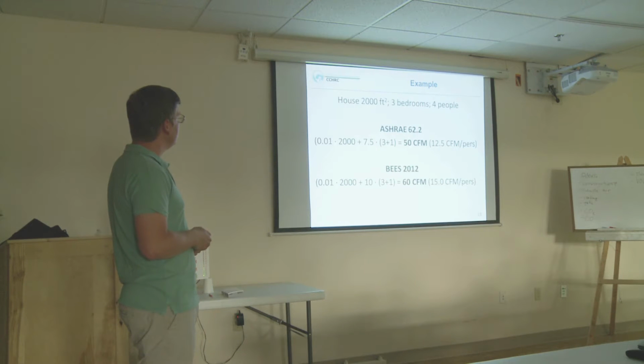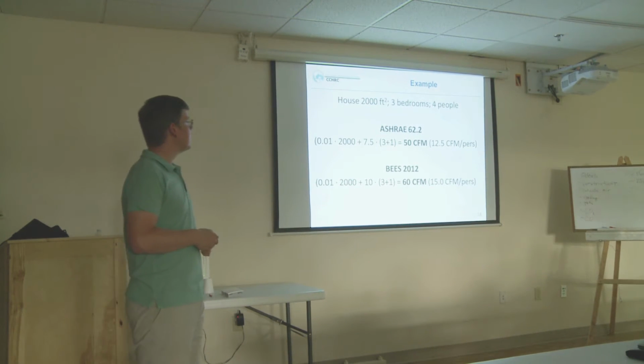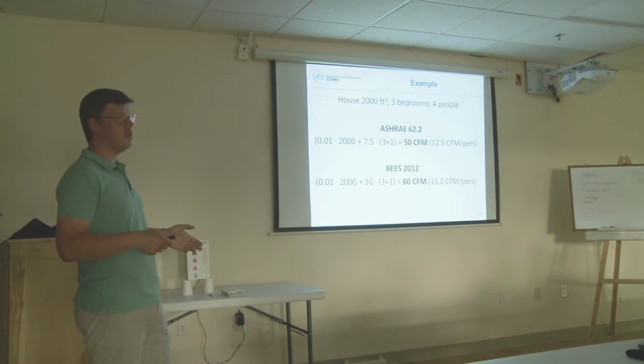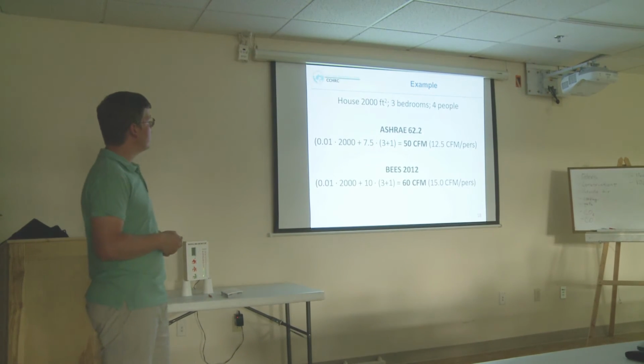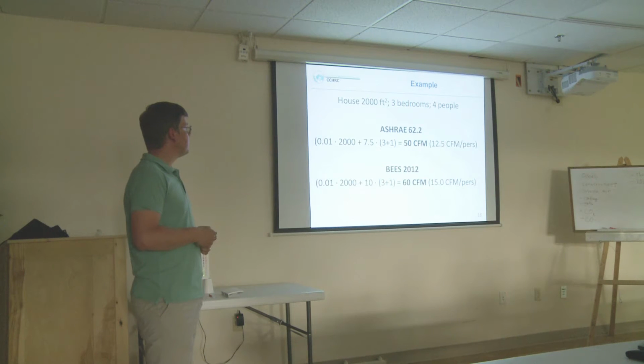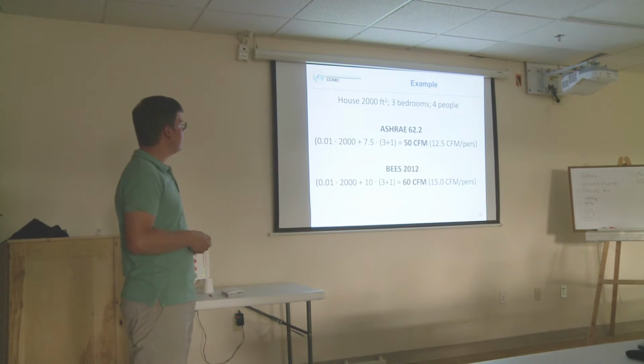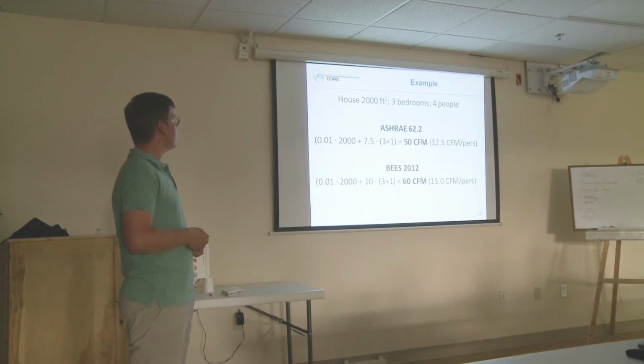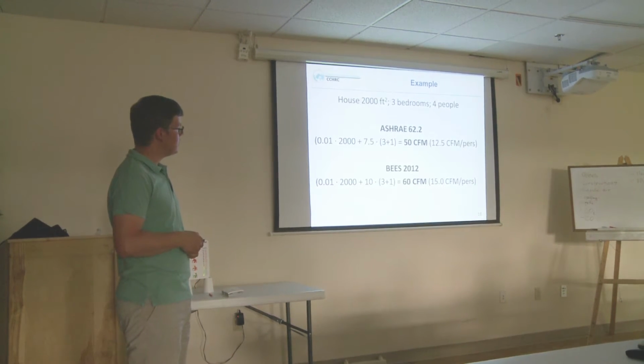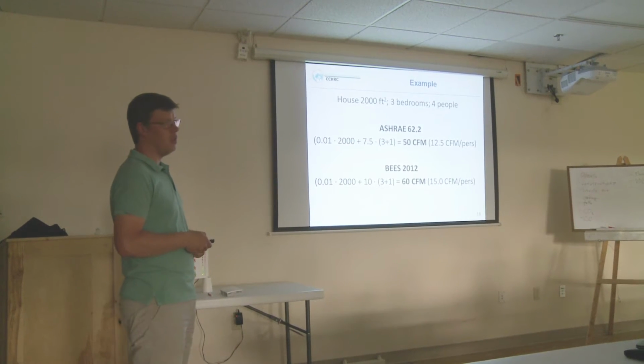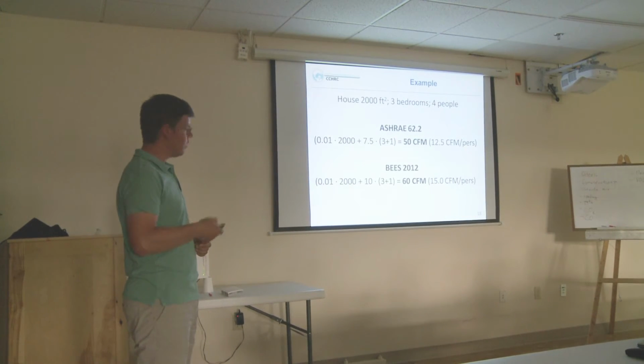If we have a house which is about 2,000 square feet, has 3 bedrooms and 4 people living in it, using the formula we get about 50 cubic feet per minute, which is 12.5 per person. And if we use the actual bedrooms, then we get 10 cubic feet per minute more, and that's the 15 CFM required by the European standards as well.